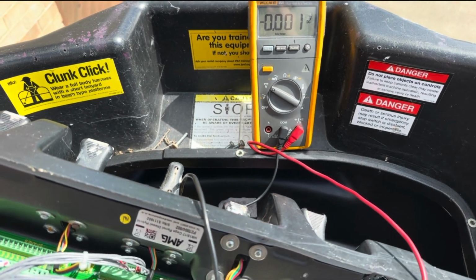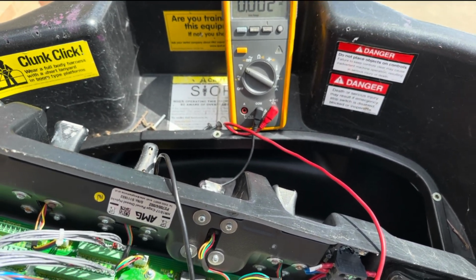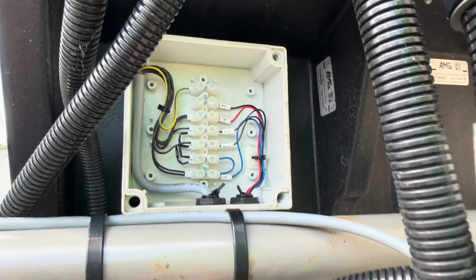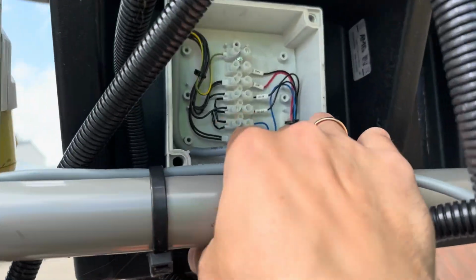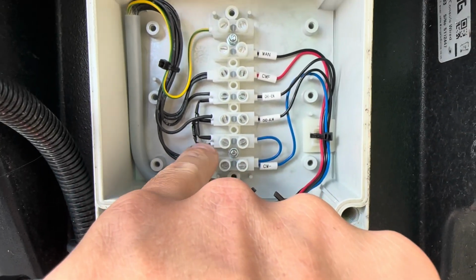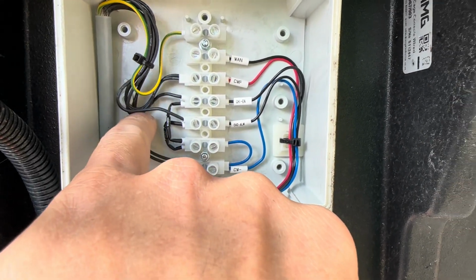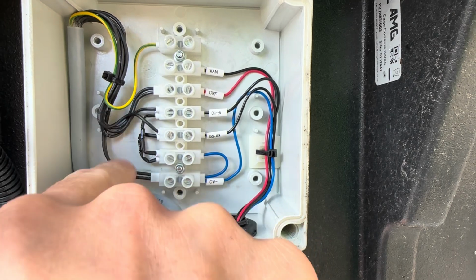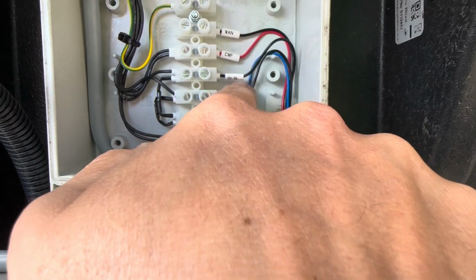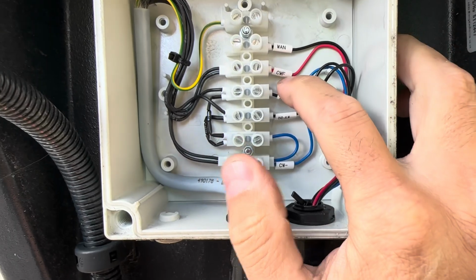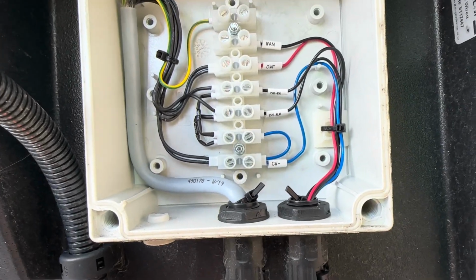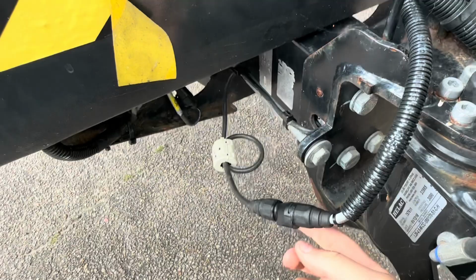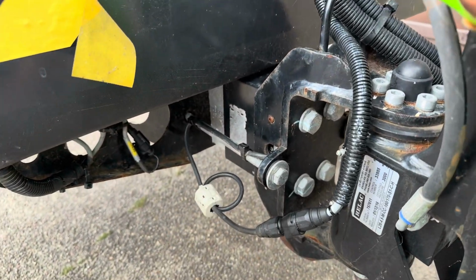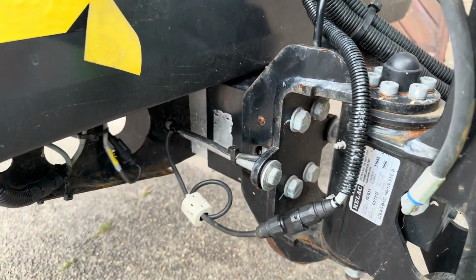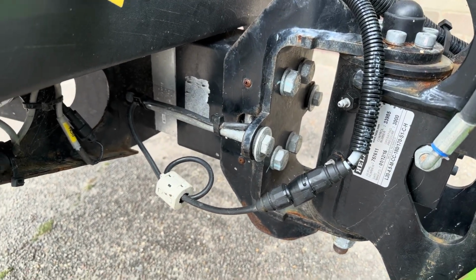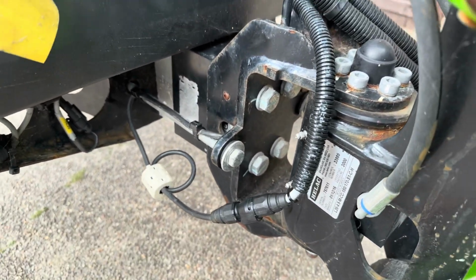So let's have a look into the resistor box, just check if everything is okay there. So here at the back of the console we have this box. Inside the box are two resistors, so that they do current to voltage conversion basically, and these are the channel 1, channel 2 wires. So all that seems to be okay here. The power supply on the red, so it seems like there are no issues here. So I think it's actually the fault with the load cell, this one here. So I think I'm going to have to change that and run calibration, and hopefully that's going to solve the problem.